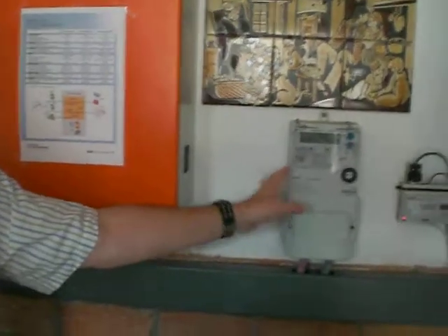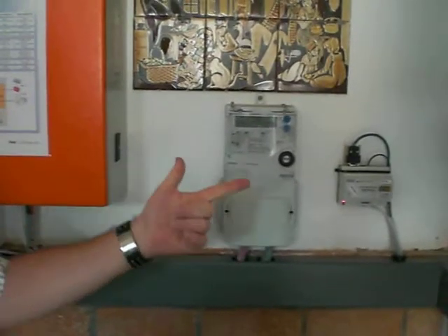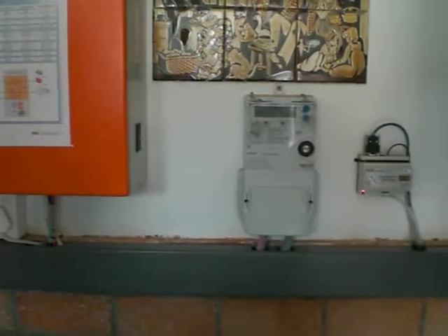it's not exactly like this, but more or less. So the power comes in. It gets split to the feed-in meter, which is the main municipal meter outside the door you came in, and this feed-in meter is this one here. So that actually records the power going in. It's a 3-phase meter where they've just used 2 phases to measure the wind, so they can measure it separately. It gets logged onto the municipal data website, so on the website you can actually see how much power is generating.